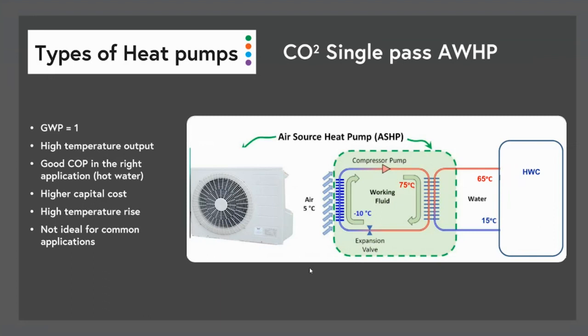Here's another one. This is a CO2 heat pump. Now, these have become quite popular in the domestic hot water space, both residentially and commercially. So CO2 heat pumps are a little interesting though. They're what's called a single pass heat pump. So they work on a big temperature difference. And so they can be quite good for things like hot water production, but they need to have load. So they need to have very low temperature water coming into them, because their temperature lift is typically somewhere between 30 and 50 degrees. So for example, on that diagram, we're showing water coming in at 15 degrees, the heat pump's lifting at 50 degrees and delivering it back to the top of the cylinder at 65.